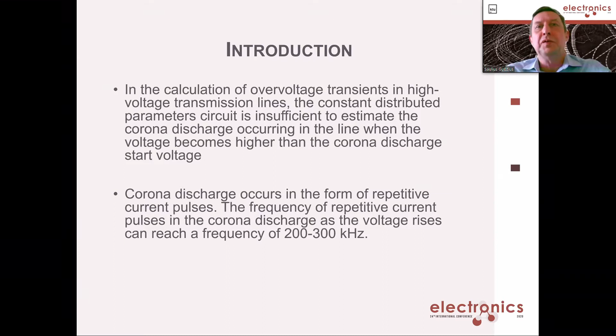So you should understand how complicated it is to model a power line, where not just the main power frequency exists. It's 50 hertz, as you know, in Europe, or 60 hertz in other countries. But if you would like to analyze processes in a power system, you must be able to register signals in very different ranges, from 50 hertz up to 1 megahertz if you're talking about lightning discharge. There are many different technologies to predict faults, to find faults, to indicate that something is wrong in the power line. But according to our experience, there is no way to use all these technologies without knowing the real processes in the power system.